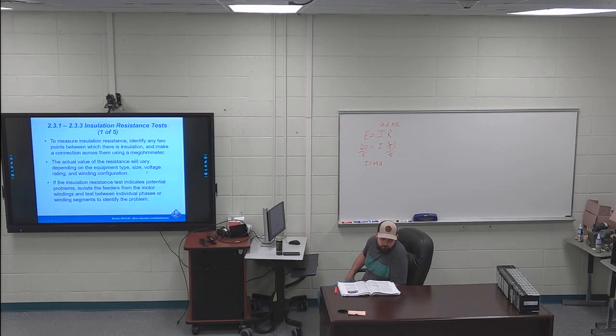So, usually you're using polarization indexes for larger motors and stuff, and you're testing the insulation over time. So you need to know, on page 22, in that paragraph right before the equation, I've got the polarization index ratio, PIR. You know what that stands for, but you need to know that the polarization index ratio is the resistance after 10 minutes versus the resistance after 1 minute. So they hold voltage on a cable for 10 minutes and see what the resistance is, and they hold the voltage on the same cable for 1 minute and see what the resistance is.